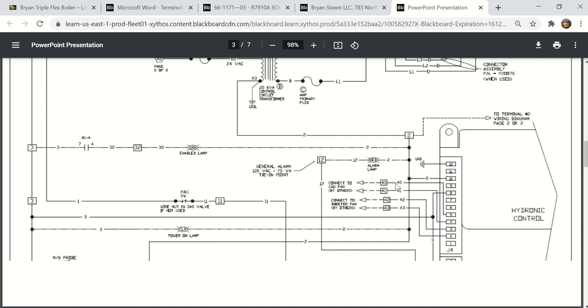While we're here, let's take a look right now at these 4 terminals here. This is field connected things that you would add to the boiler as field connected devices. One is a combustion air damper, CAD. CAD stands for combustion air damper, and then they have the term fan. A lot of times on boiler rooms nowadays, instead of just having a louver on the wall for combustion air to supplement for the air that is going up the stack, air to get in the boiler room, now a lot of times it's done with a makeup air fan.